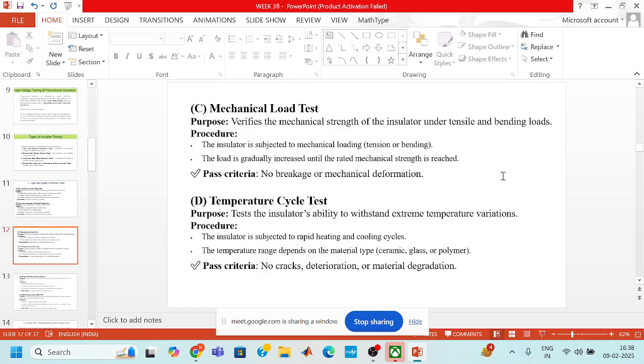Now, the third test is the mechanical load test. It verifies the mechanical strength of the insulators under tensile and bending loads. First of all, the insulator is subjected to mechanical loading such as tension or bending, and the load is gradually increased until the rated mechanical strength is reached.